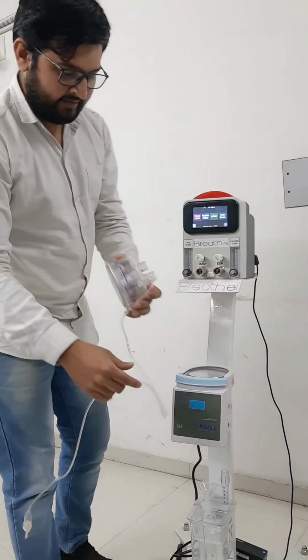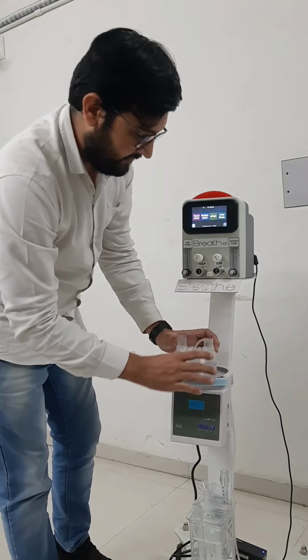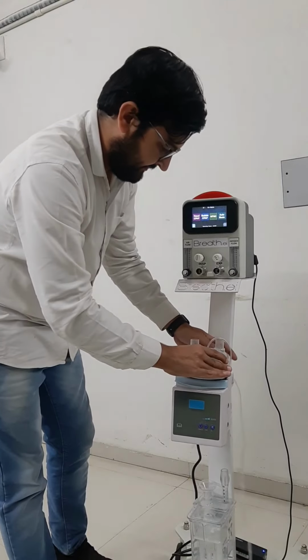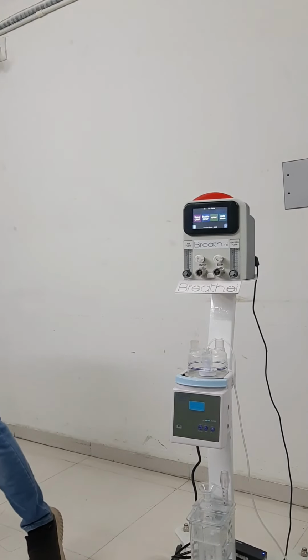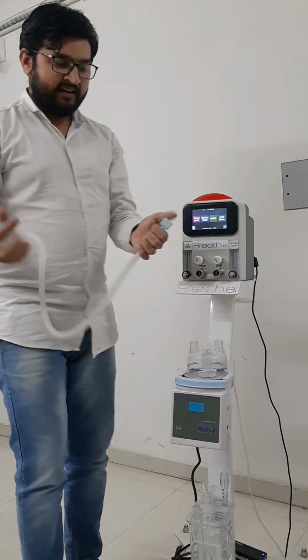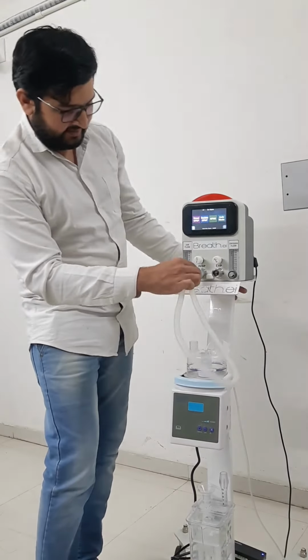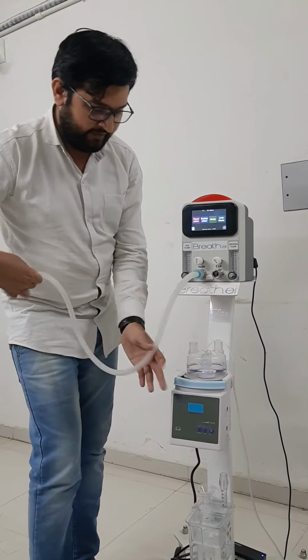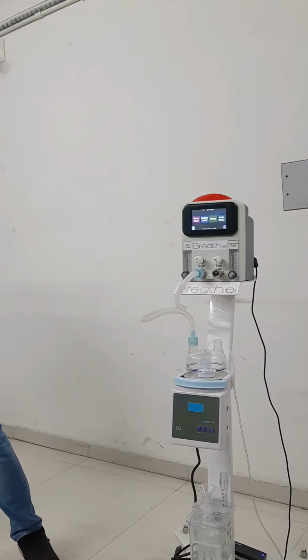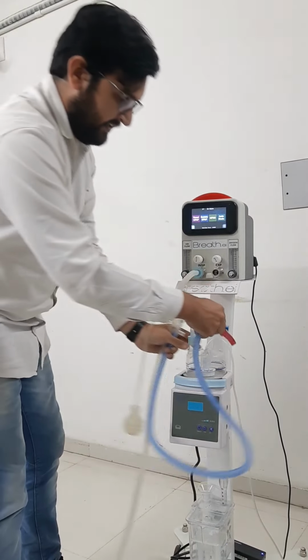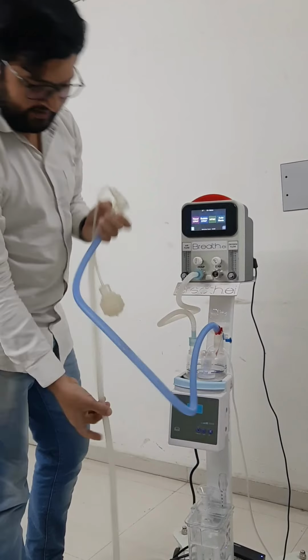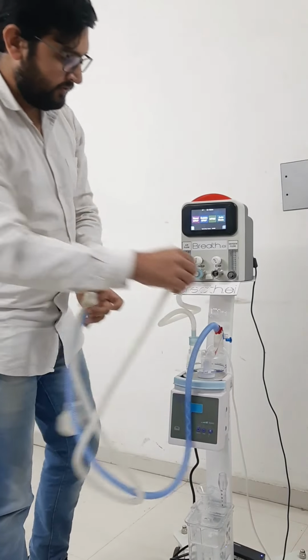For circuit connection, first of all we have to place this humidifier chamber on the humidifier. Then we have to connect the first inspiratory tube from the machine inspiratory port to the humidifier chamber. The second inspiratory tube is connected to the humidifier chamber, and the circuit expiratory limb goes to the machine expiratory port.